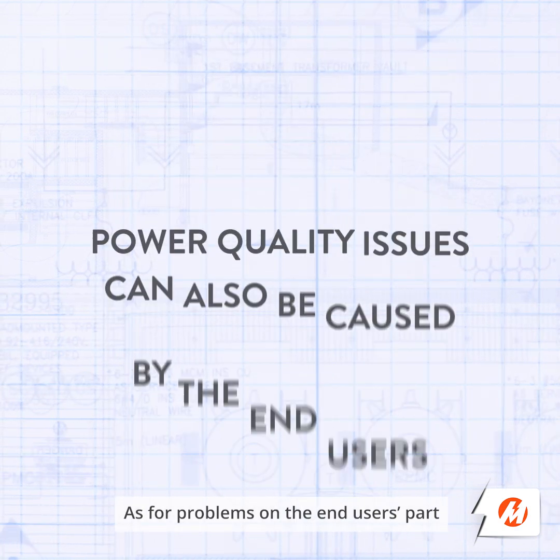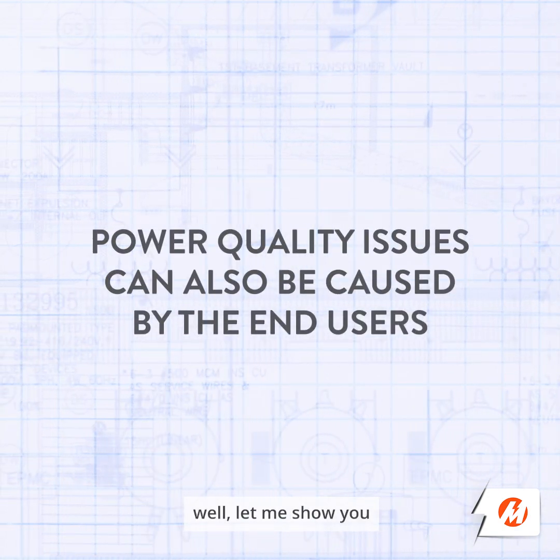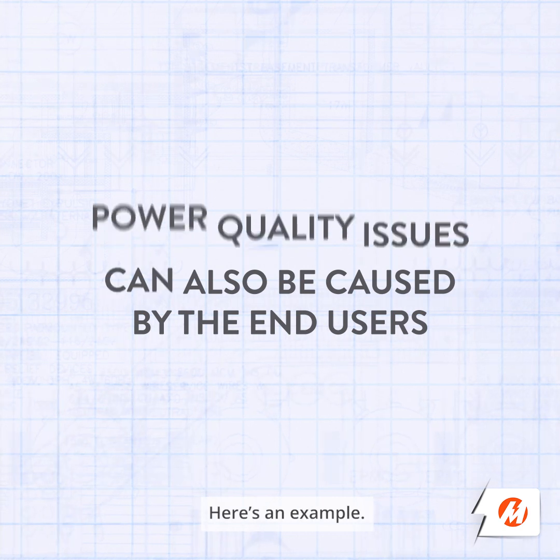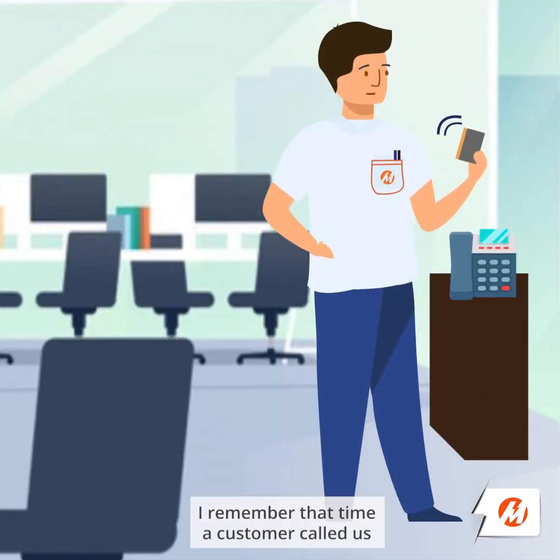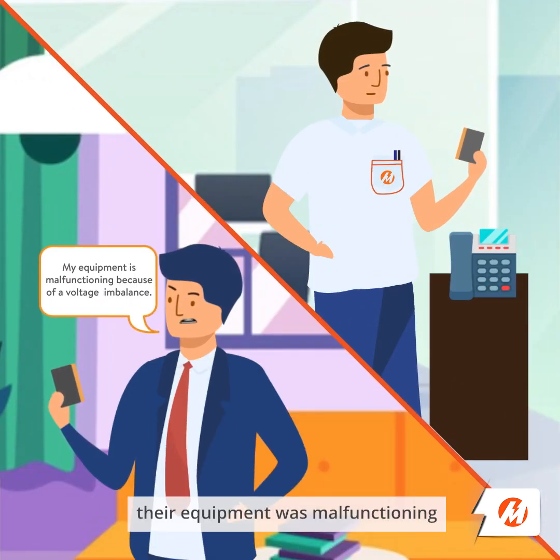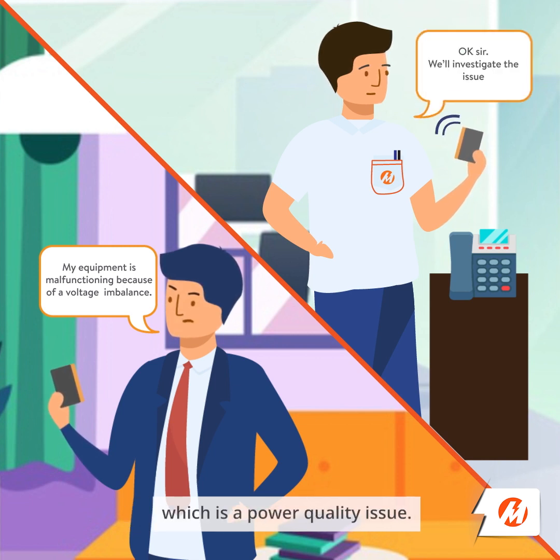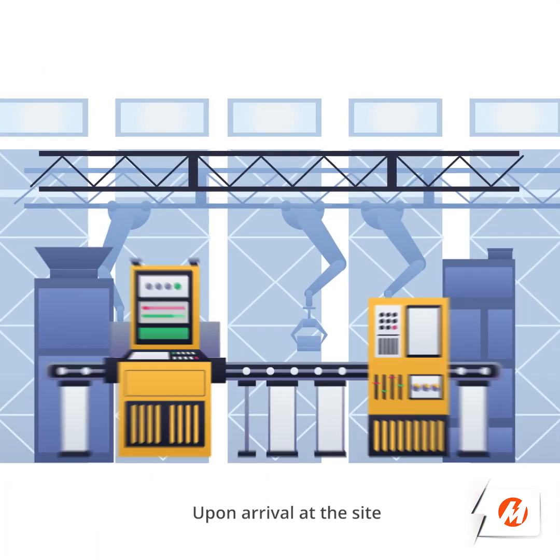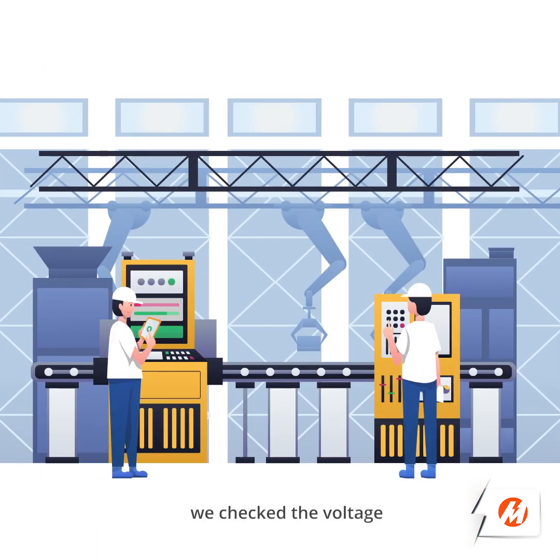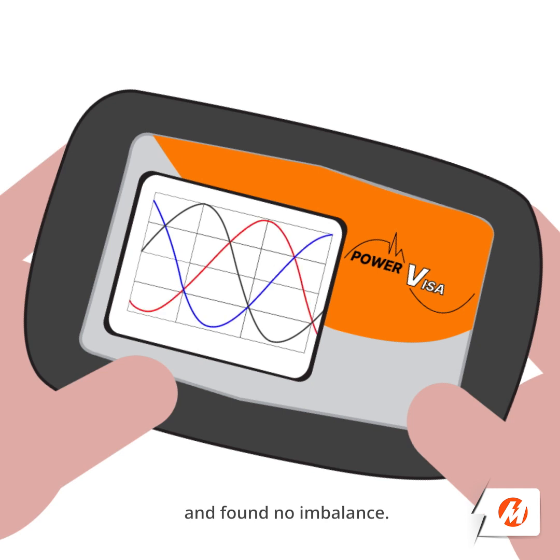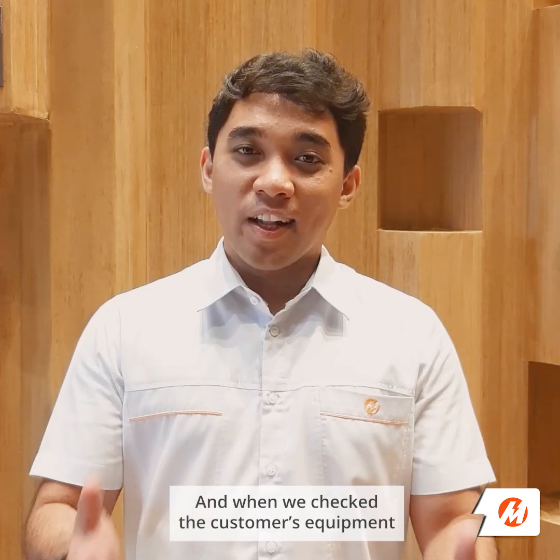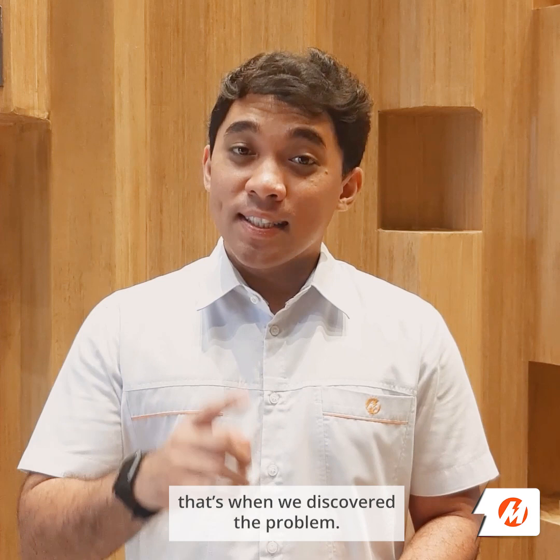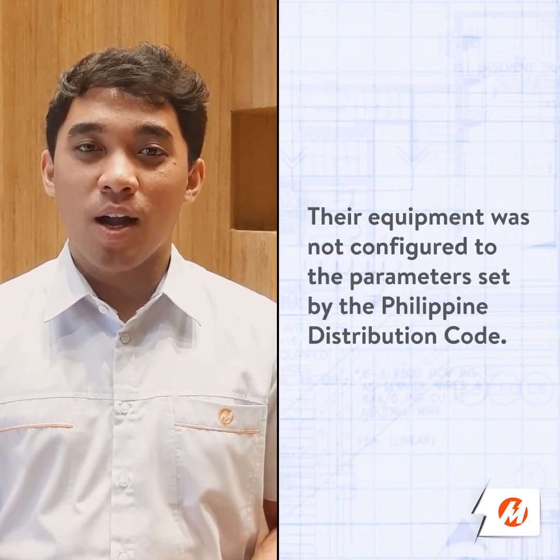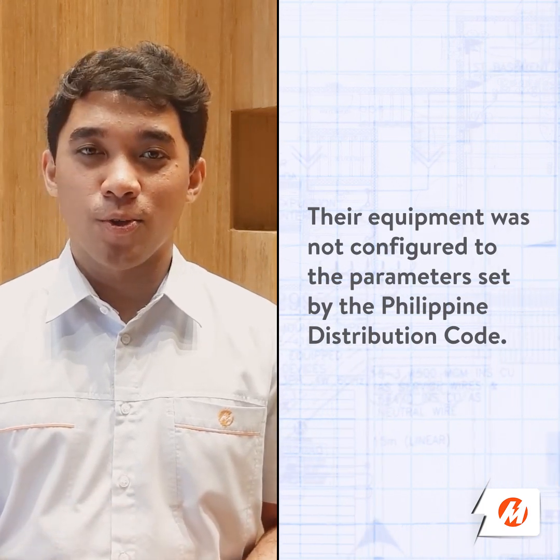As for problems on the end user's part, let me show you how that can happen. Here's an example: I remember a time a customer called us because they believed their equipment was malfunctioning due to a voltage imbalance, which is a power quality issue. Upon arrival at the site, we checked the voltage and found no imbalance—it was as it should be. When we checked the customer's equipment, that's when we discovered the problem: it was not configured to the parameters set by the Philippine Distribution Code.